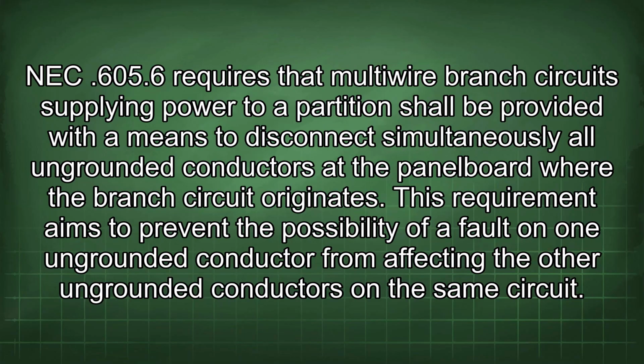NEC 605.6 requires that multiwire branch circuits supplying power to a partition shall be provided with a means to disconnect simultaneously all ungrounded conductors at the panel board where the branch circuit originates. This requirement aims to prevent the possibility of a fault on one ungrounded conductor from affecting the other ungrounded conductors on the same circuit.